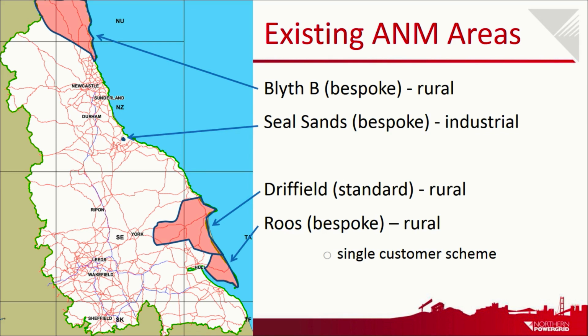In the Blyth area in Northumberland, we've got 500 megawatts of generation being controlled, where there's a limiting factor of 480 megawatts in the winter on the national grid interface transformers, the supergrid transformers at the grid supply point. But we've also got some limitations on the circuit. So if we lose a circuit, we need to get all the generation in the group down to 240 MVA in the winter, or 220 MVA in the summer.